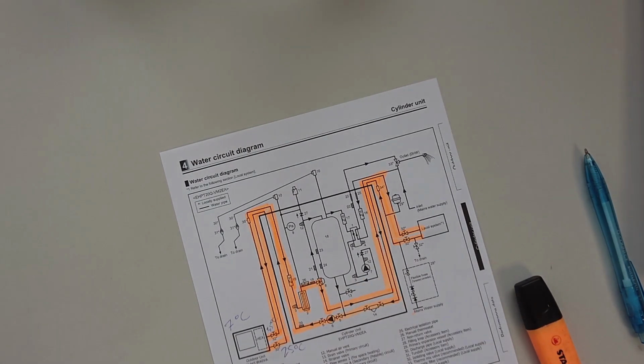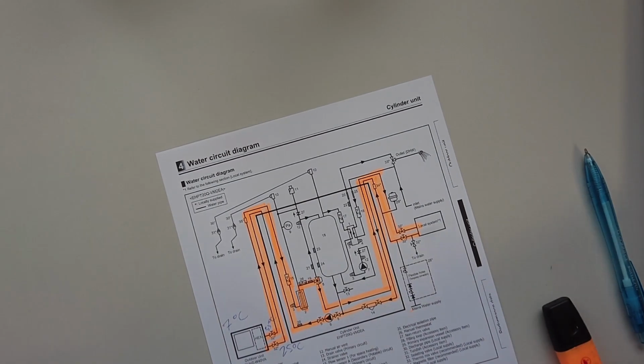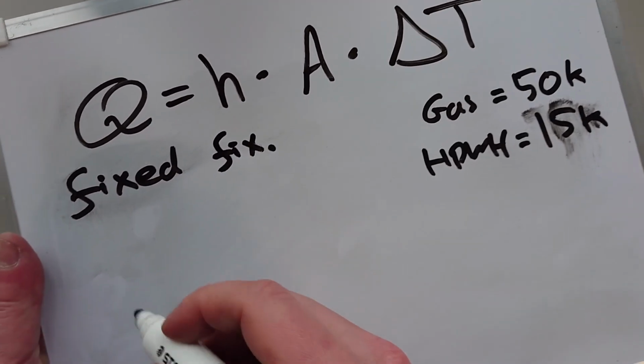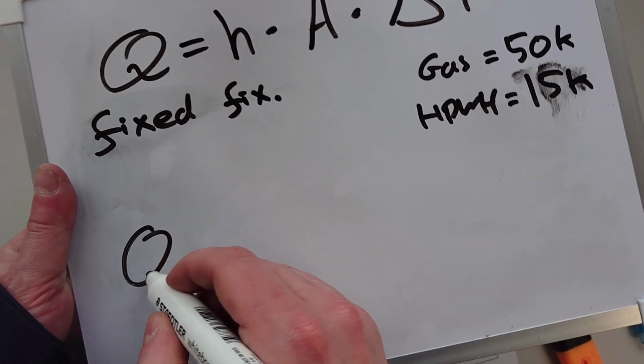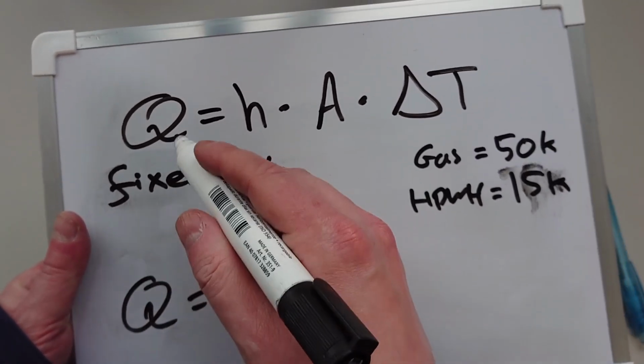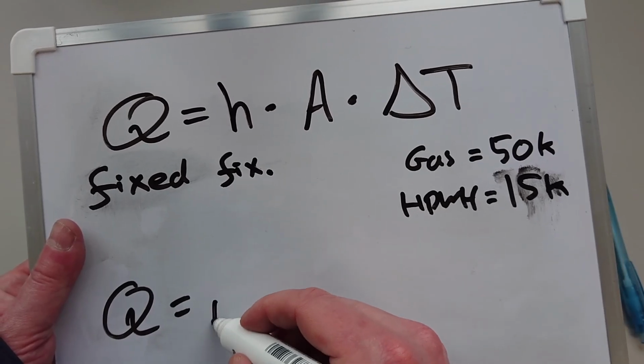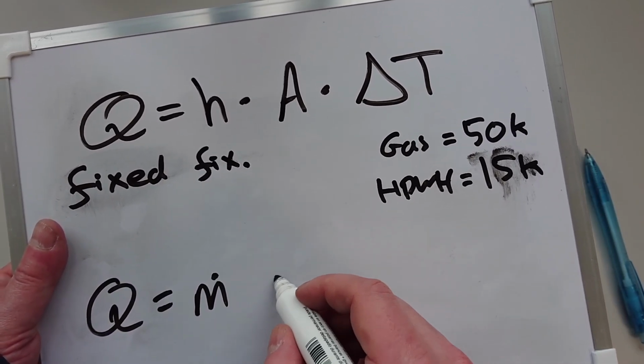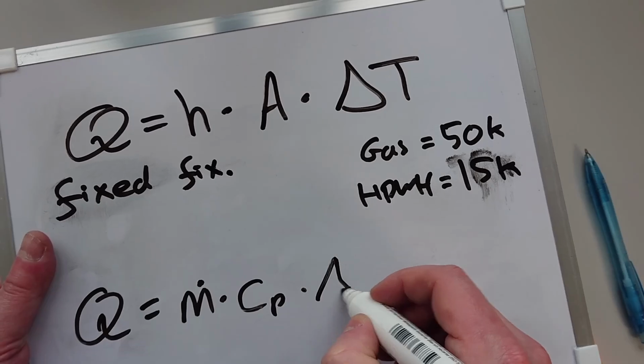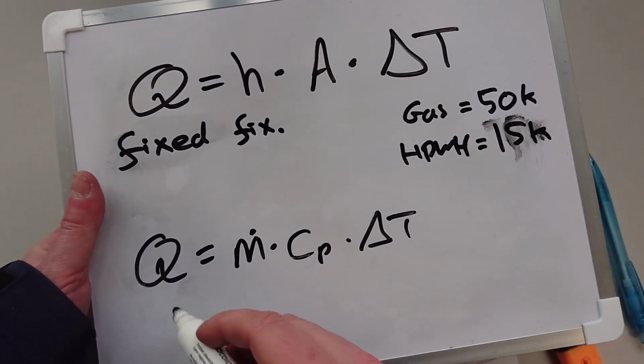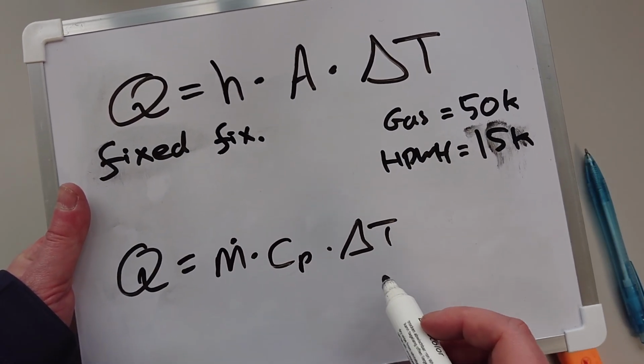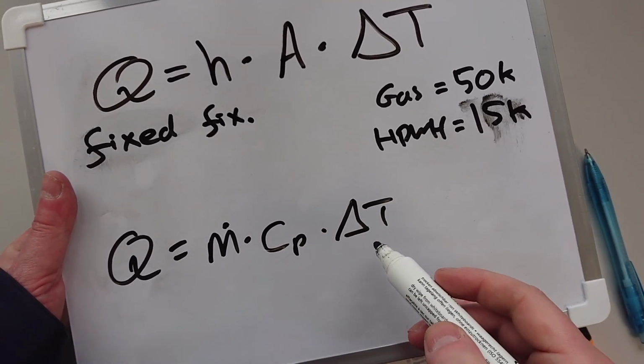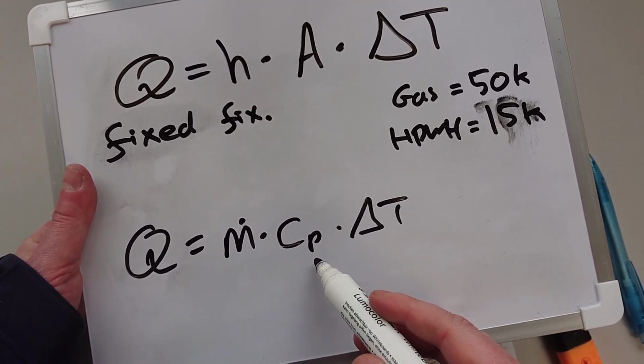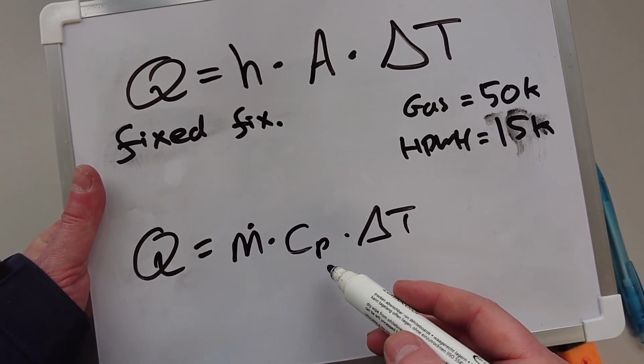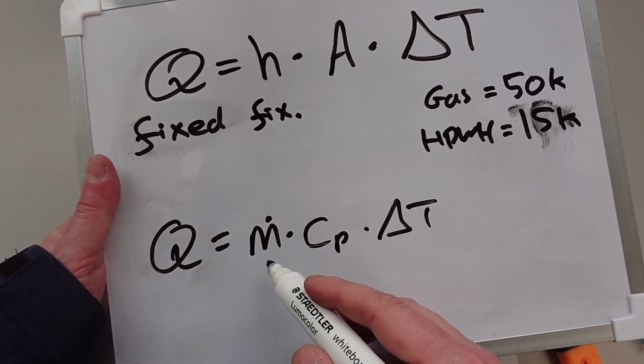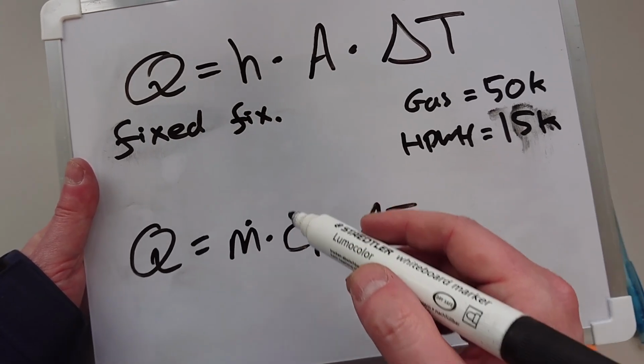So now we've got that out of the way as to why you can't just heat it up more. What you've then got is the heat exchange from the water side, and we can say that Q, the heat again, which is still fixed, is equal to the mass flow of the water times the specific heat of the water times the delta T of the water. Well, now the Q is fixed, the delta T is relatively fixed by the outside temperature and our efficiency. The specific heat is fixed, it's just 4.2 for liquid water, which is what it is going in and out. So now all you can do is vary the mass flow. So now you have to put the mass flow up.